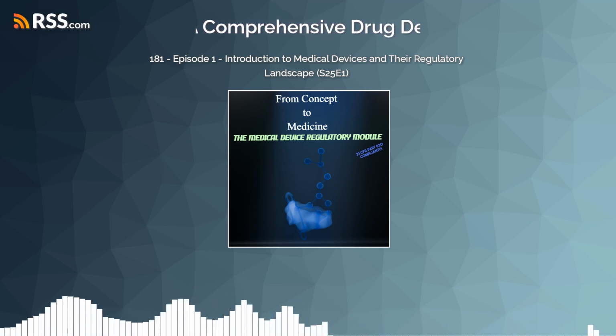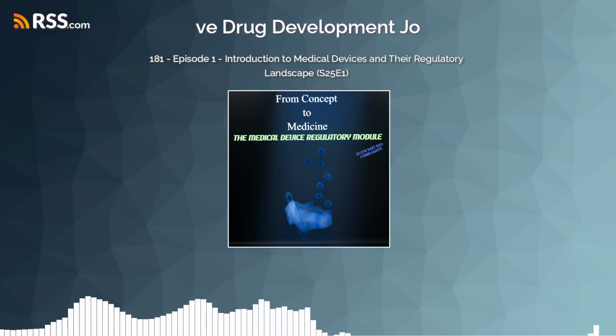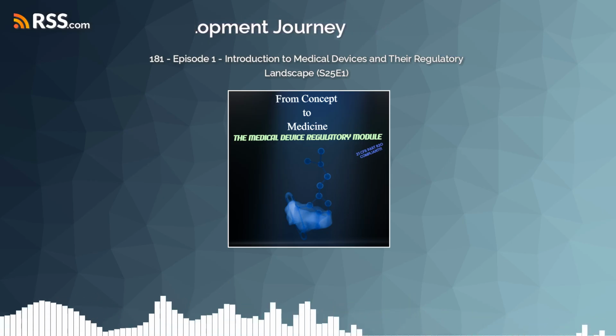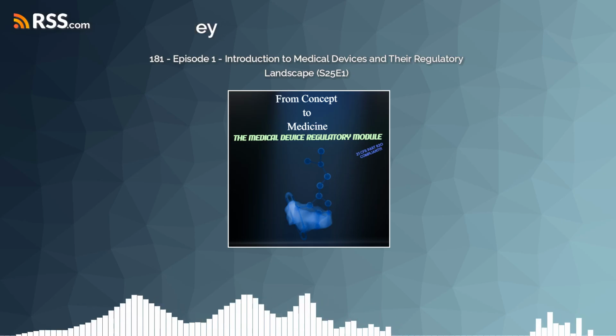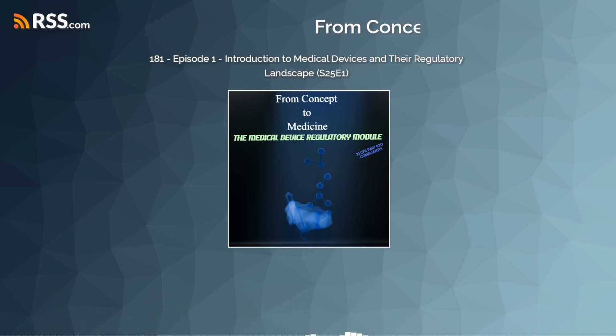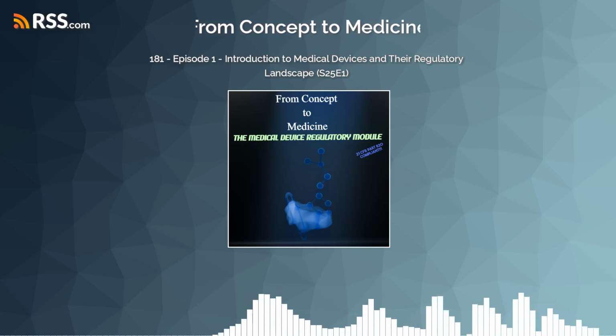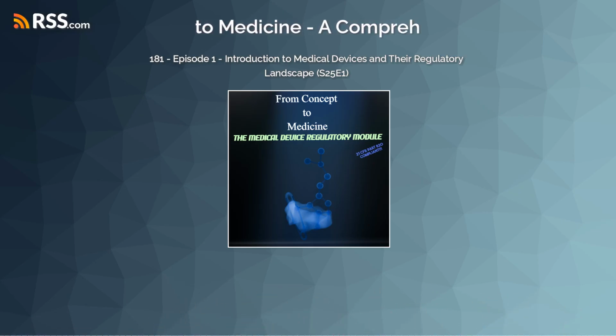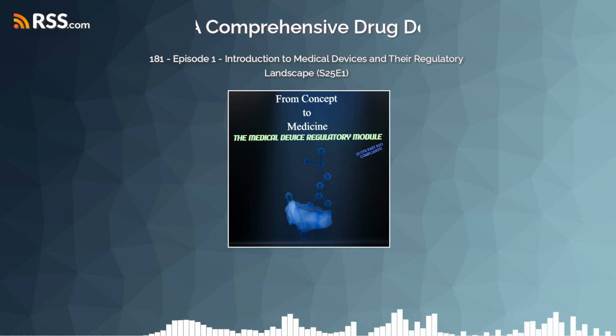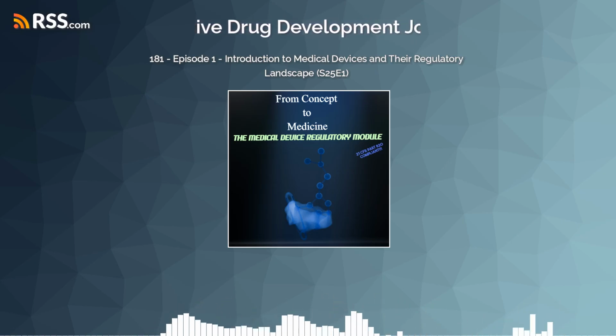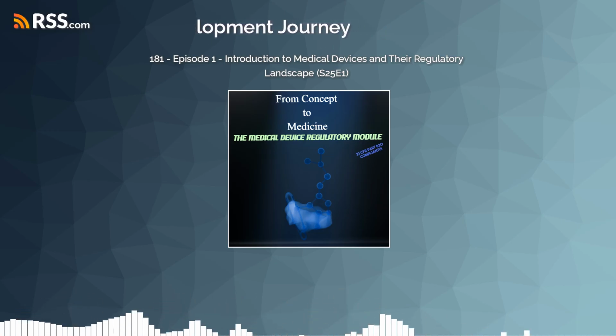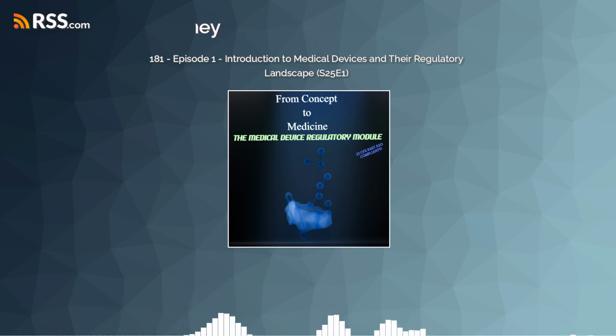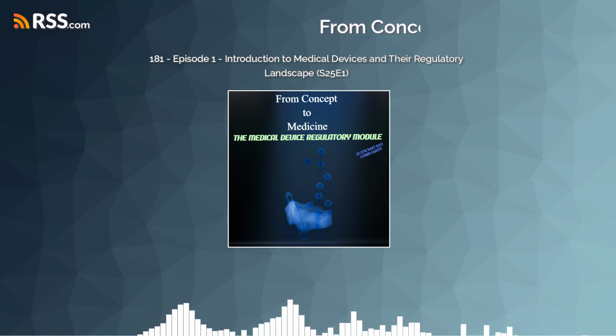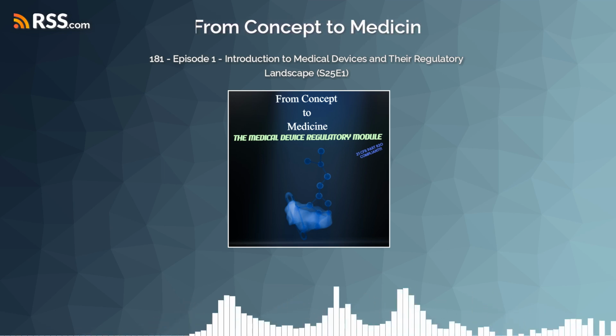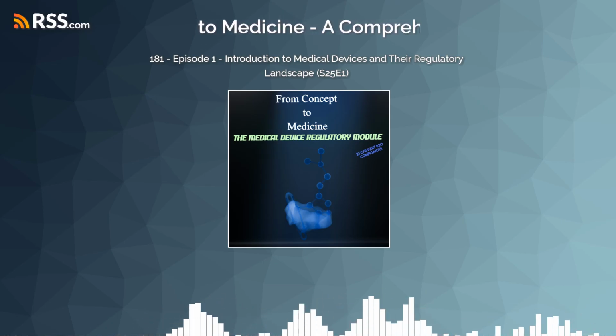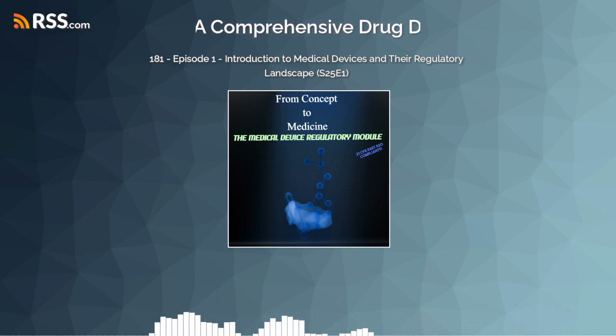We've talked a lot in past deep dives about good clinical practice, or GCP, for pharmaceuticals, often referencing the ICH E6 guideline. Is there a similar standard specifically for device trials? There is, and this is another key difference from the drug world. While pharma trials largely follow ICH E6, medical device clinical trials primarily adhere to ISO 14155 for good clinical practice. Okay. It's an international standard that covers device trial design, conduct, performance, monitoring, auditing, recording, analysis, and reporting. The FDA recognizes this standard, so data gathered under ISO 14155 can support regulatory submissions in the U.S.